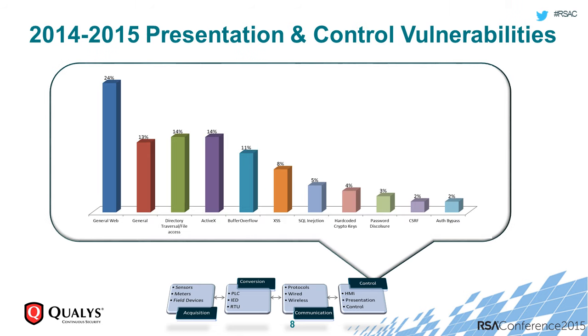And finally, going to the last component — presentation and control. This was a surprise to us. We went into this research expecting that there would be a lot of sensor and PLC-type vulnerabilities. But the surprise was that most of the vulnerabilities we found were in the data presentation or the HMI layer. These vulnerabilities are very similar to what we see on a day-to-day basis in IT infrastructures — vulnerabilities in web applications, thin clients, cross-site scripting, SQL injection, directory traversal, and so on.